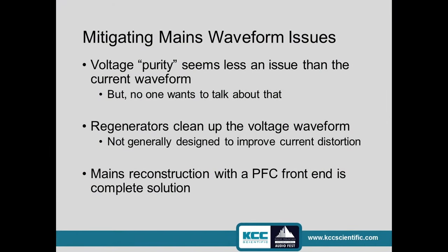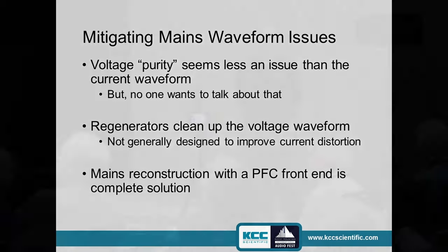How do you mitigate these issues? I don't understand why nobody wants to really talk about the current waveform when the voltage and current waveforms are directly related — in a non-linear way in most power supplies. Regenerators are a great idea for cleaning up the waveform, absolutely — but they're not really designed to improve the current distortion, so that's always going to still be there. It may be that mains reconstruction with a PFC front end is the only way to cure this ill, or we can continue to ignore it.